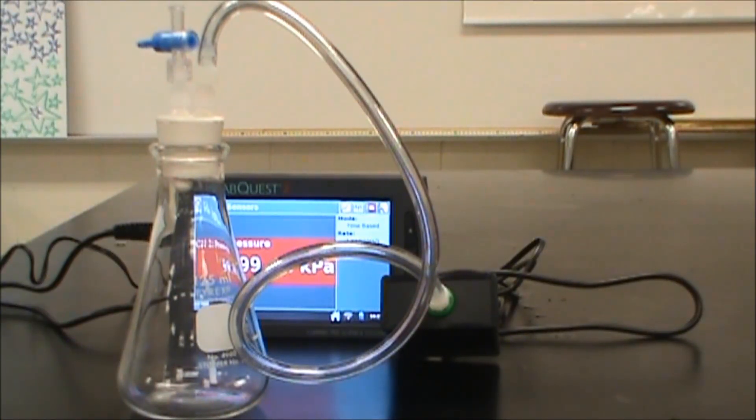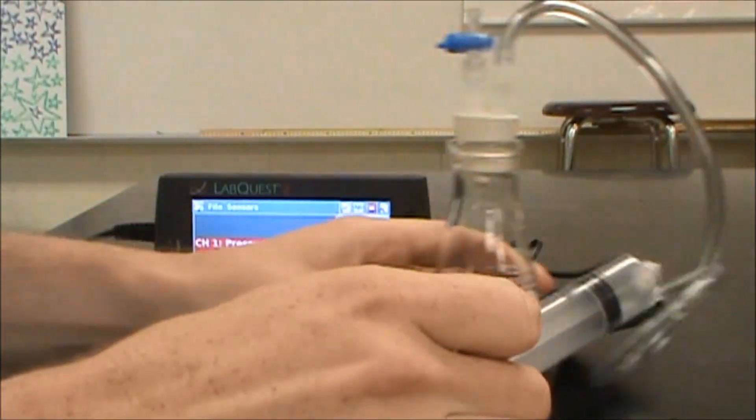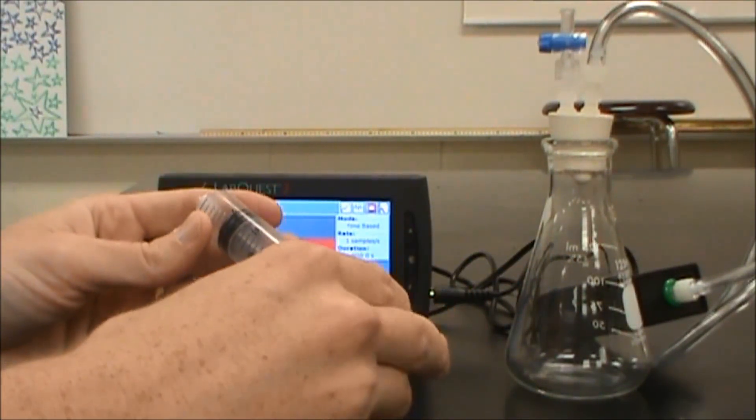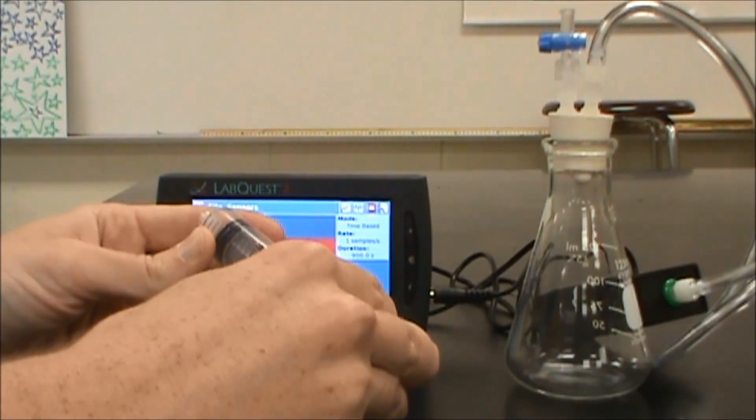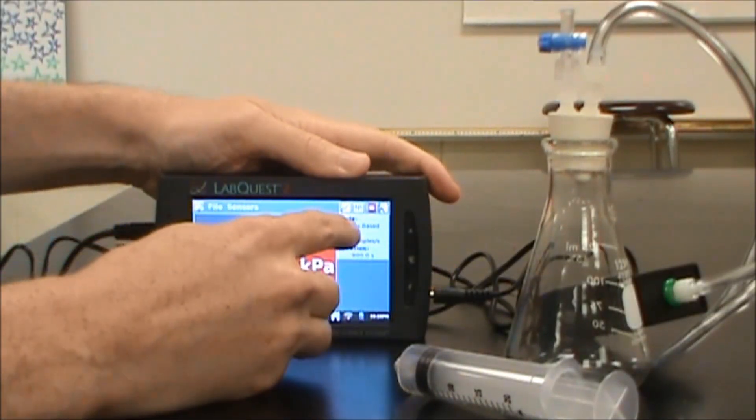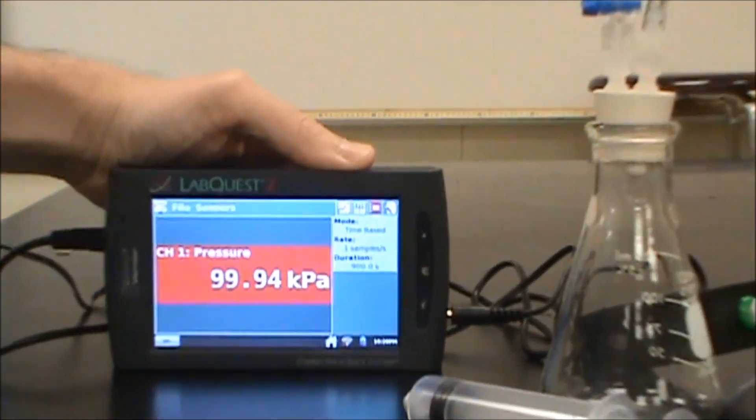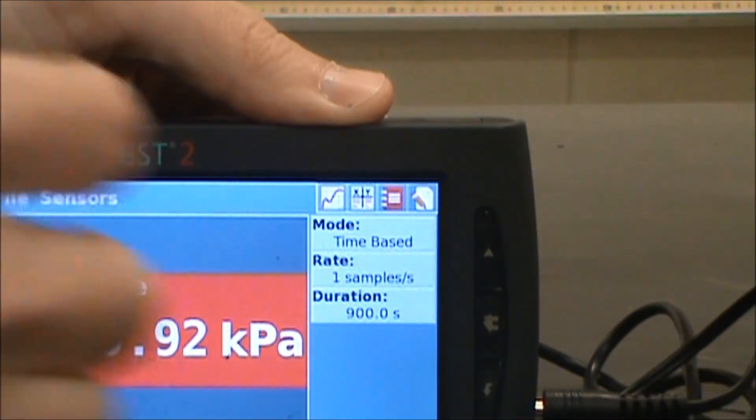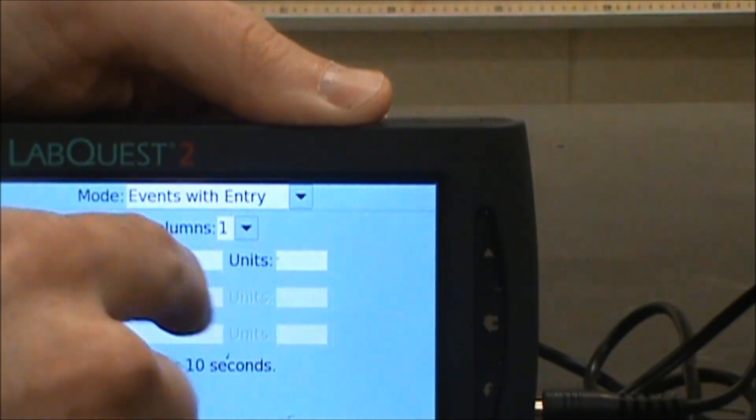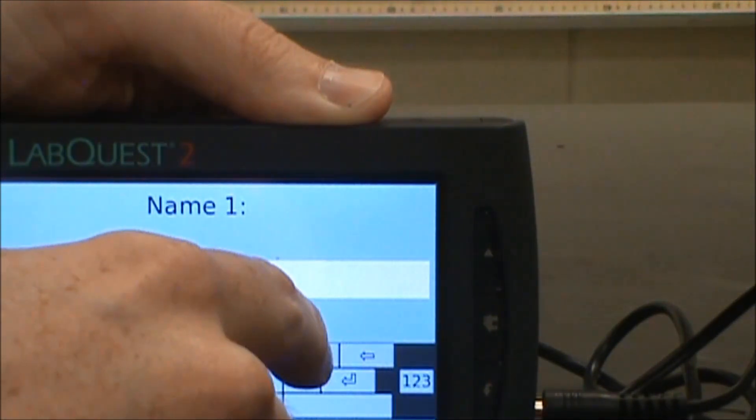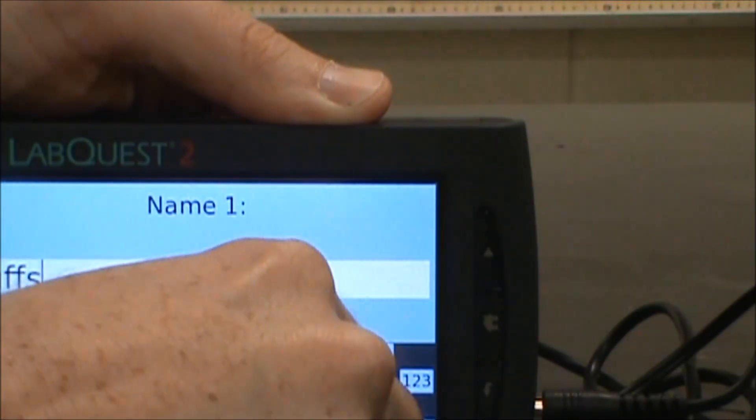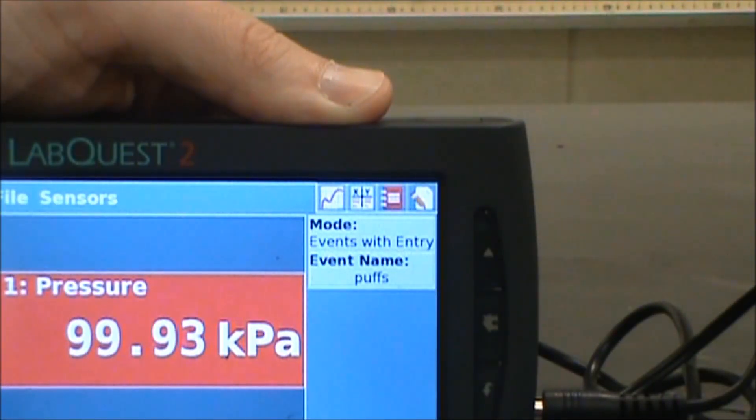What you're going to do on this is you're going to add air to this, where you're going to take your syringe and put so much air. We're going to put five milliliters of air or four milliliters or three or whatever. I want to go to where it says mode and time-based. Let me scoot in here. Where it says time-based for mode, I'm going to take that and change that to events with entry. That way I can get a plot of this. For events name, I'm going to put puffs. Done. OK.